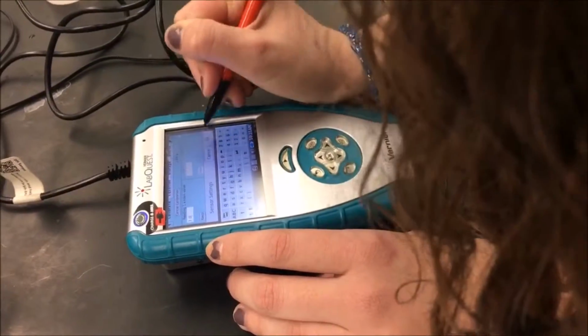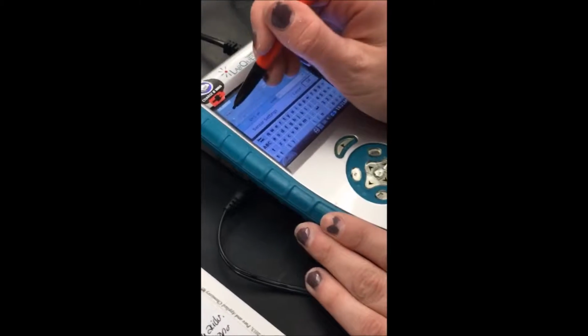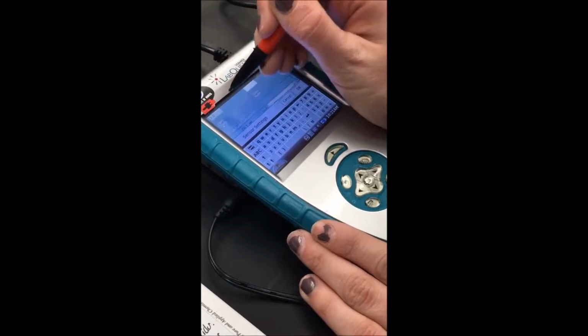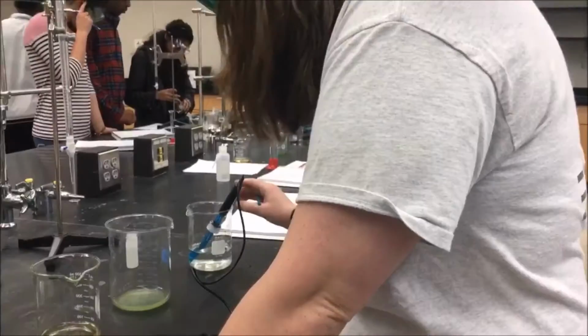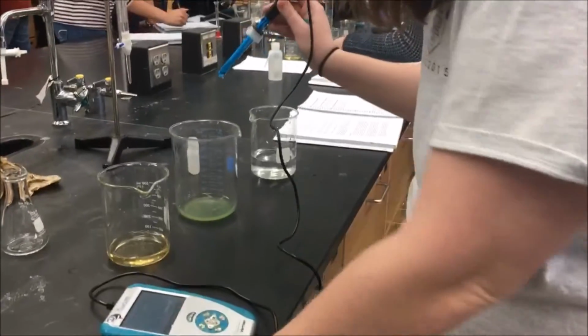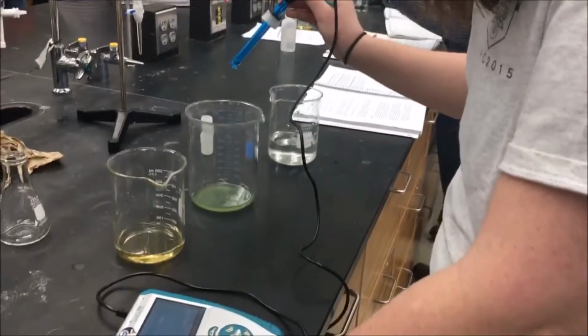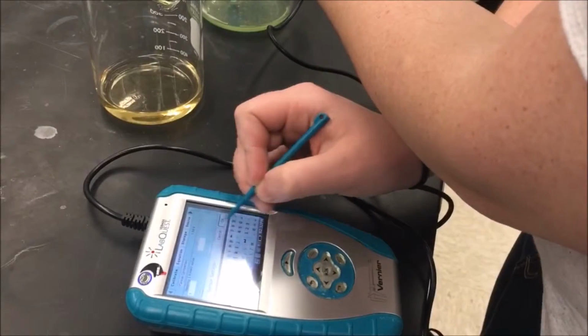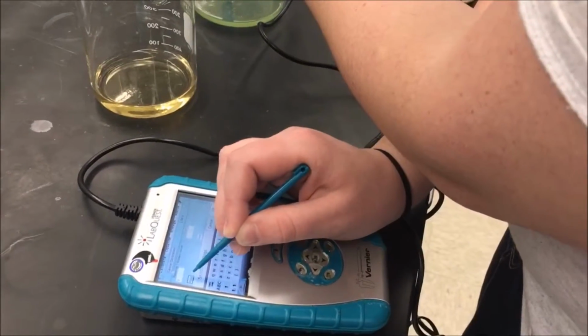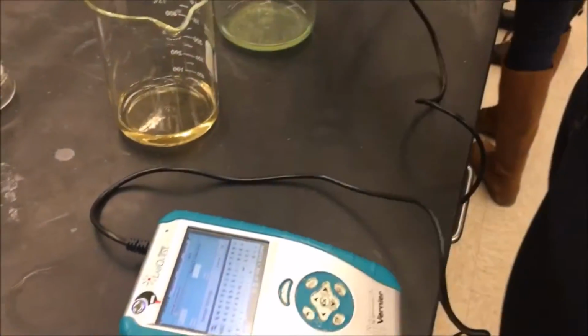First, place the probe in a beaker filled with a pH 4 buffer. Then, wait for the value to stabilize on the screen and insert the value 4 and hit Keep. Then, rinse off the probe with the provided wash bottle of water while holding over an empty beaker. Shake off the excess water.